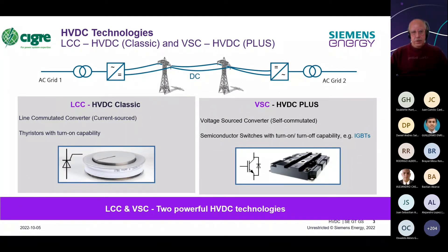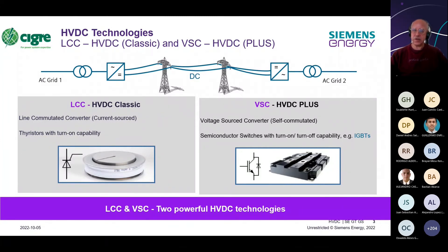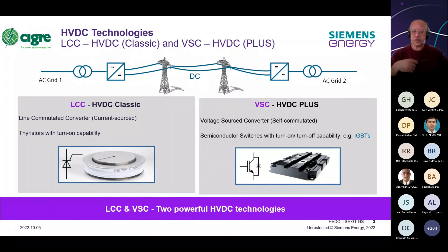The main difference between LCC and VSC stems from the switching device. In LCC technology, thyristors cannot reverse current direction, so to reverse the power direction, the voltage polarity of the converter must be reversed. In VSC, the current direction can be changed directly, allowing power to flow from station two to station one by simply reversing current direction.